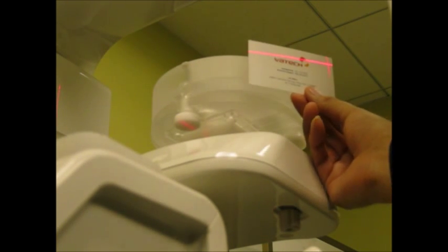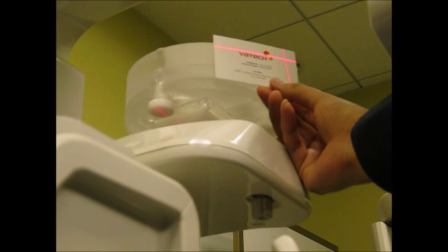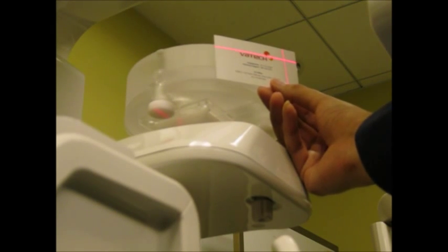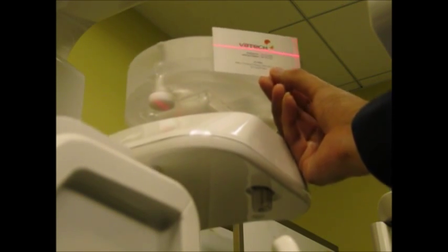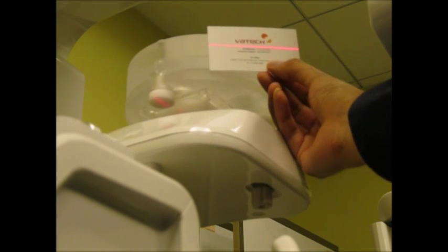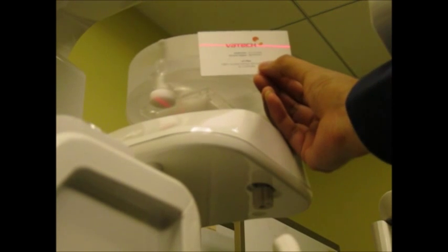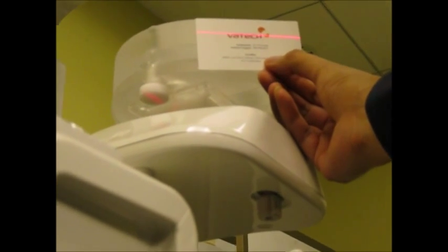It's a bubble. Just make sure that you identify the number of the jig, because those numbers need to be positioned the same way. So the jig is 0, this level is number 1, and all those numbers on the phantoms need to be aligned with each other.